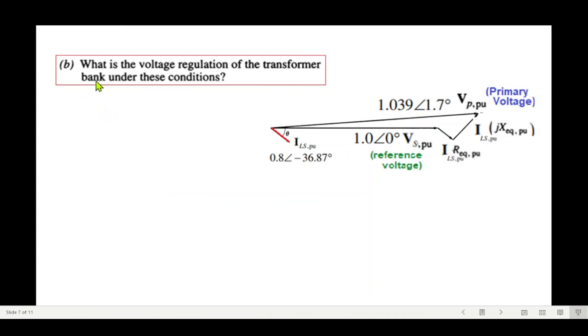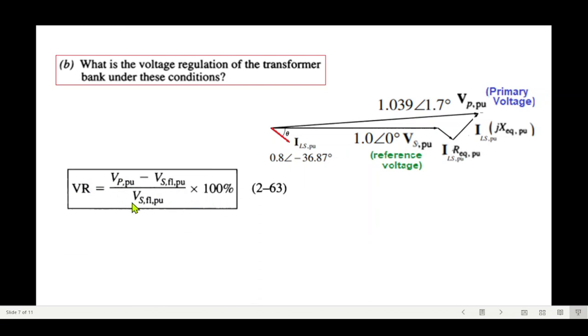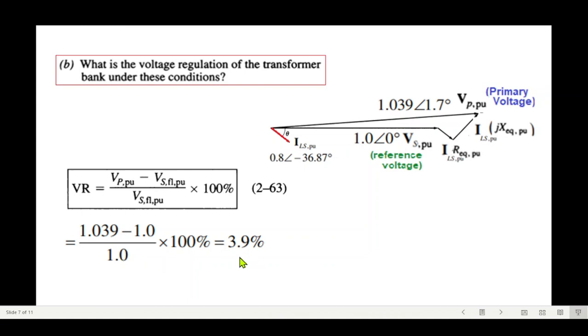Part b: what is the voltage regulation of the transformer bank under these conditions? The per-unit voltage regulation formula is VR = (V_P_pu − V_S_pu) / V_S_pu at full load. With V_S_pu = 1 and V_P_pu = 1.039, the voltage regulation is 3.9%.